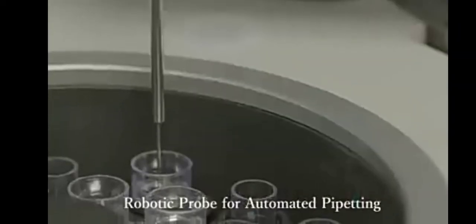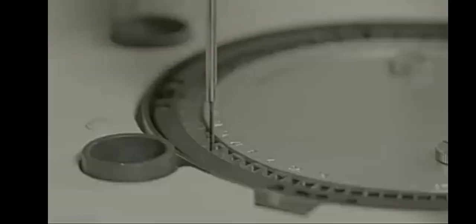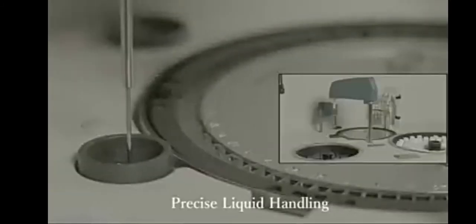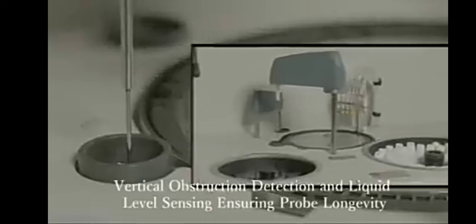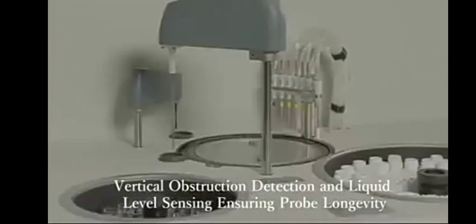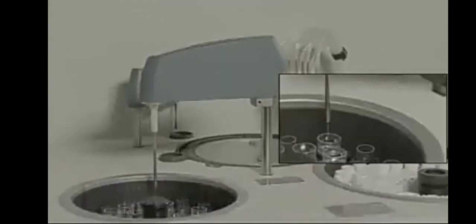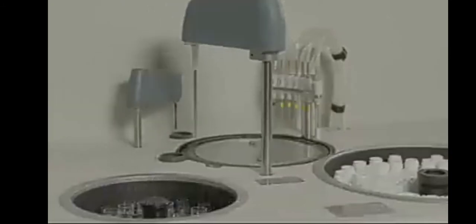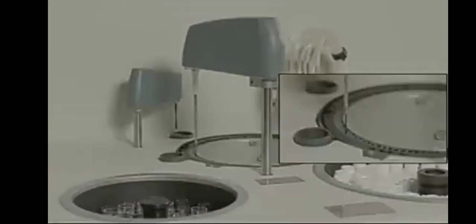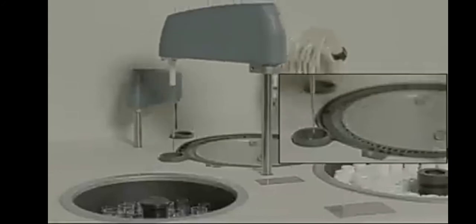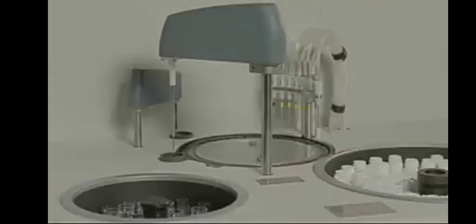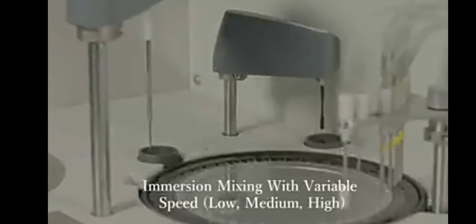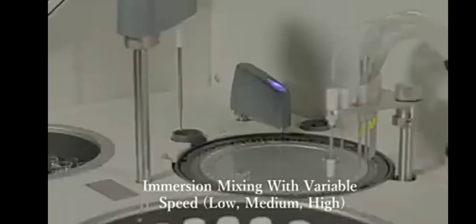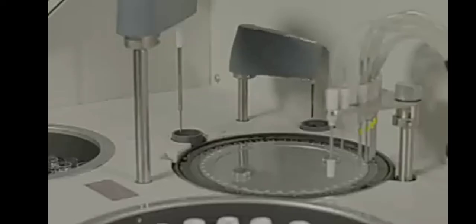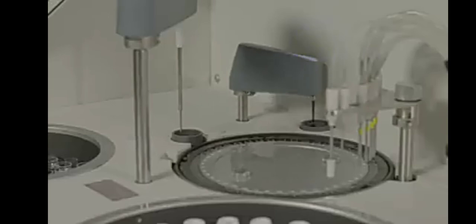Equipped with an advanced robotic probe for automated pipetting of reagent and sample, ensuring precise liquid handling. Vertical obstruction detection sensor protects the probe. Ensuring accurate performance of specialized chemistries, including immunoturbidimetric assays by thorough mixing.